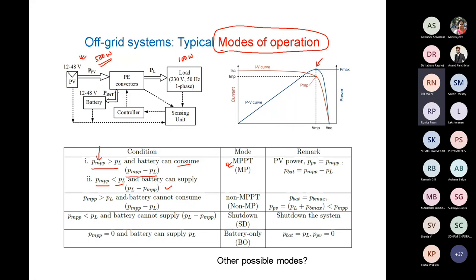But let's say I'm operating in MPPT mode and a situation arises where PV power is more than load demand, and the battery is already charged. It cannot consume that extra power. So what should I do? If I dump that extra power into the battery, the battery will overcharge and get damaged. It is risky for life also.